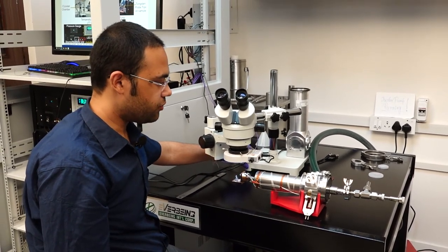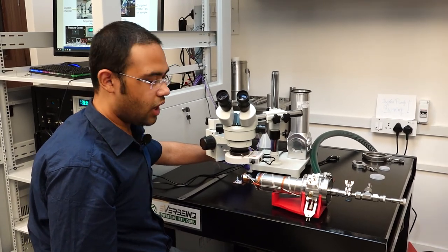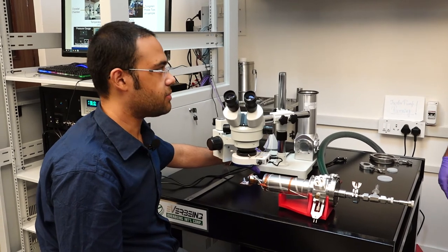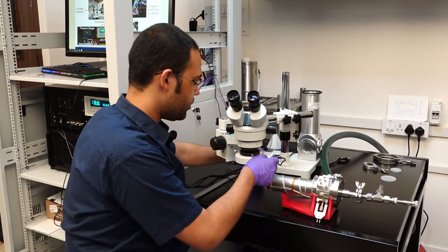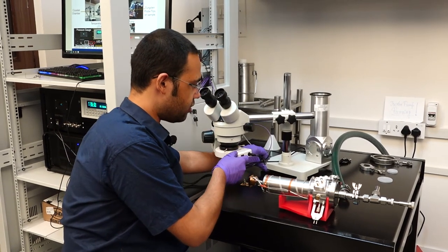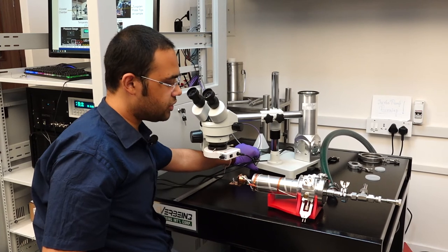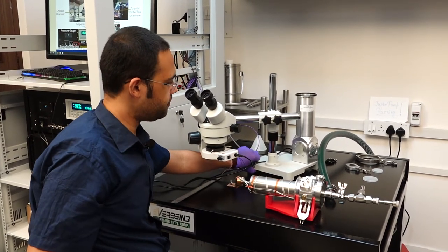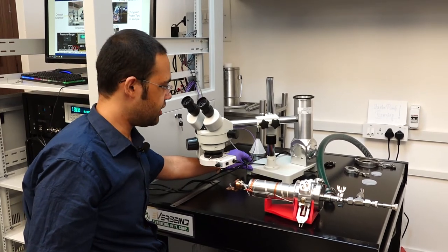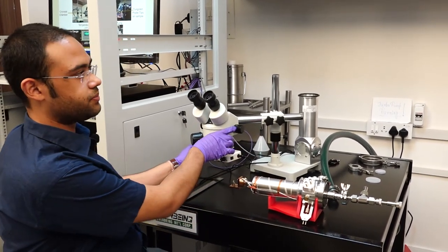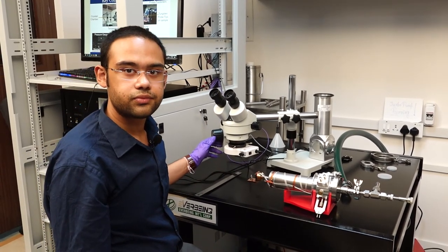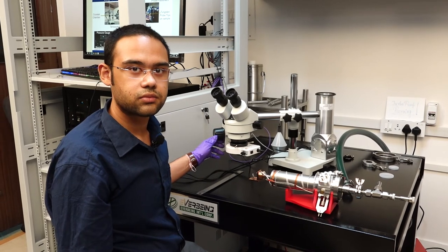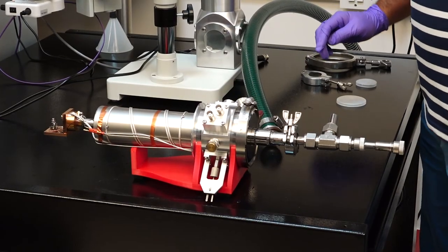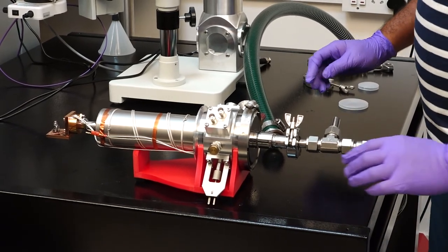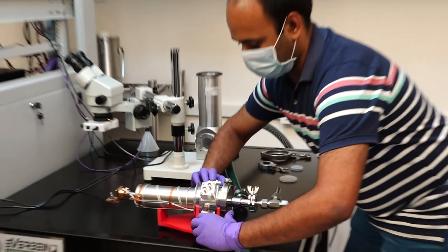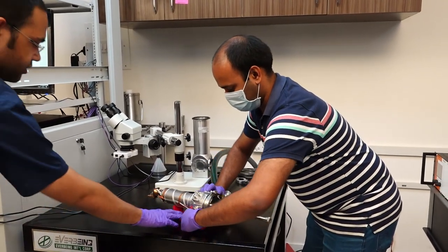Once our sample is probed, we generally do an IV CV measurement that I will show you in the subsequent modules. For the time being, once we check that all the things are in place, we would now put this stage back into this cryo holder, and we would then seal it off as shown in the subsequent steps. Okay, so now we will demonstrate how to carefully load this sample holder stage into the cryo chamber.